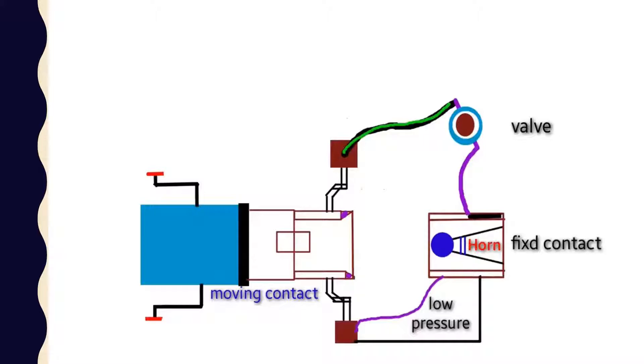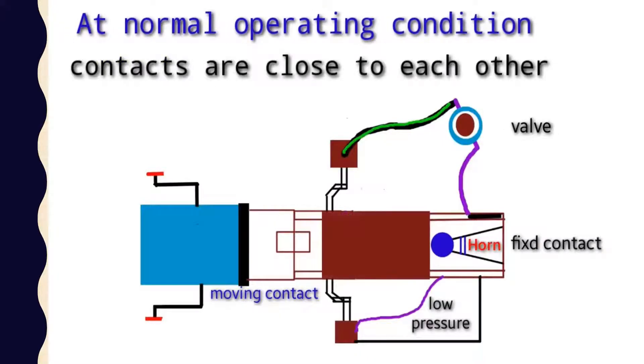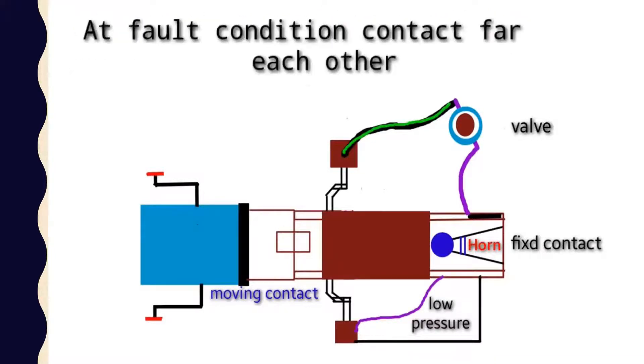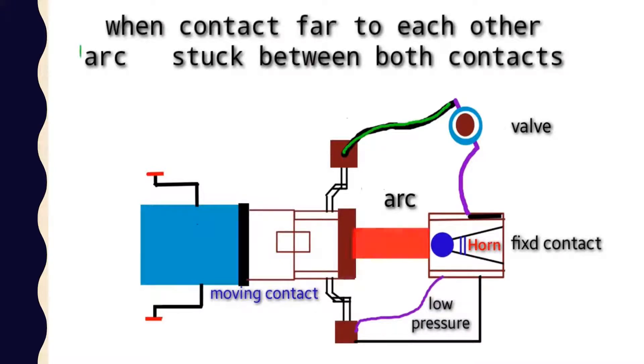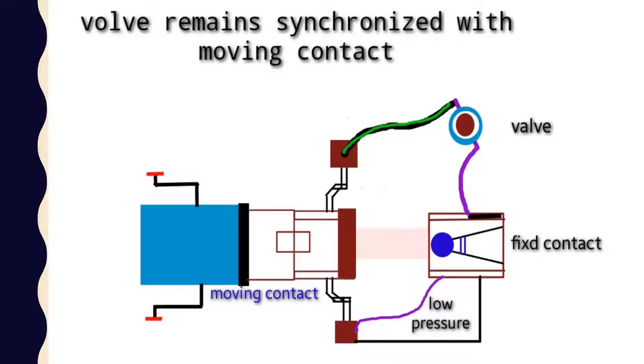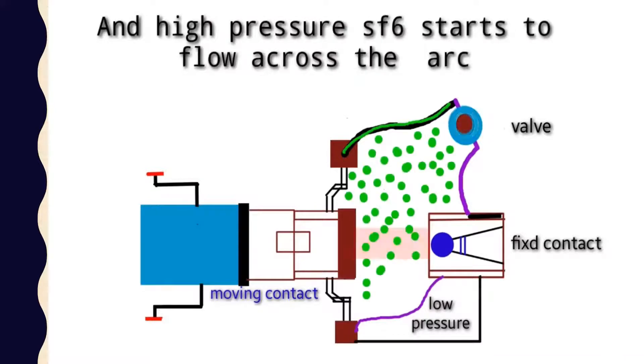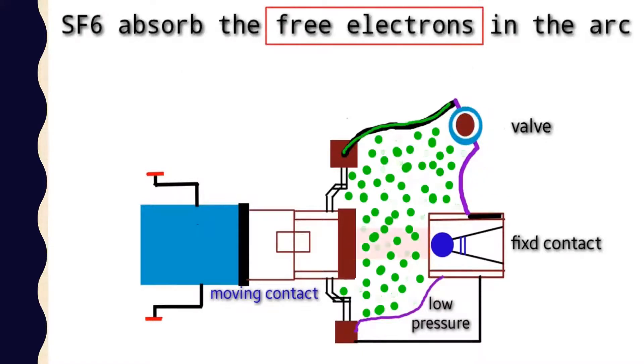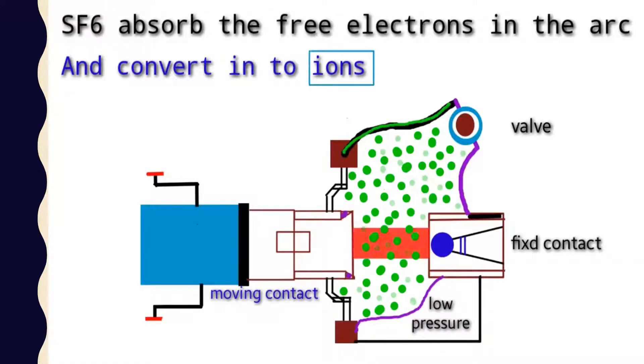Here you can see clearly. Under normal operating conditions, both contacts remain closed. As soon as any type of fault occurs in the system, both contacts separate from each other. As soon as both contacts separate, an arc is struck there. Since the moving contact is synchronized with the valve, as soon as the moving contact moves, the valve also opens, and high pressure SF6 gas begins to flow across the arc. The free electrons in the arc are absorbed by the SF6 gas.